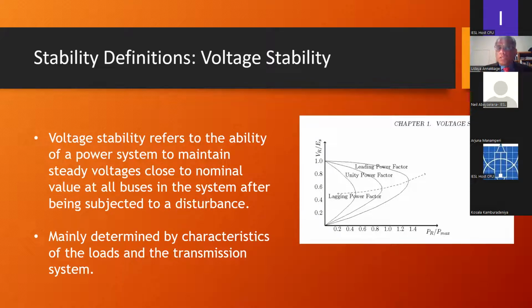Now, what can happen in a system is you can suddenly lose one component of the network. Maybe you lose one transmission line, one transformer, or any component. That changes the topology of the system. And as a result, the maximum power transfer capability limit can decrease. And if your load is still below the new maximum, that's fine. If your load happens to be higher than the new maximum, of course, that load doesn't exist. What happens is the load will decrease almost instantaneously, and the voltage level will go down.